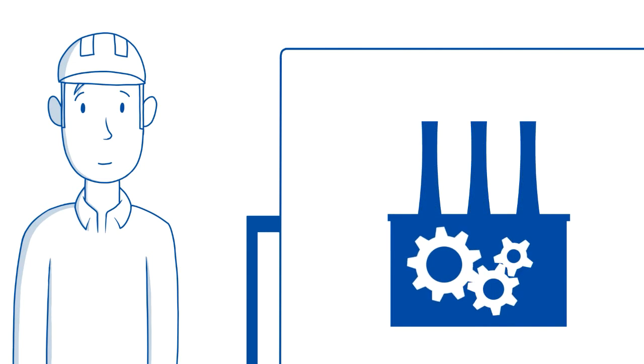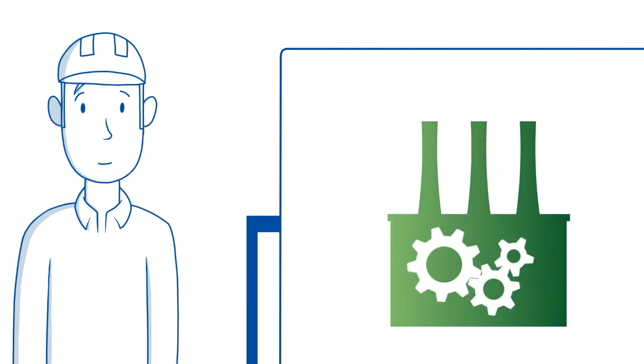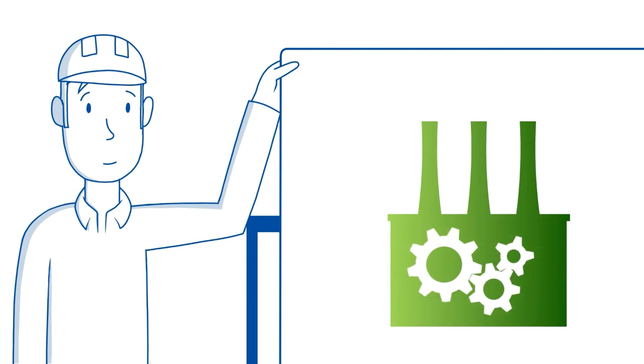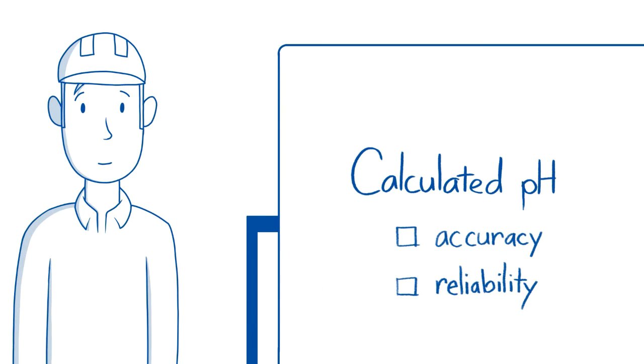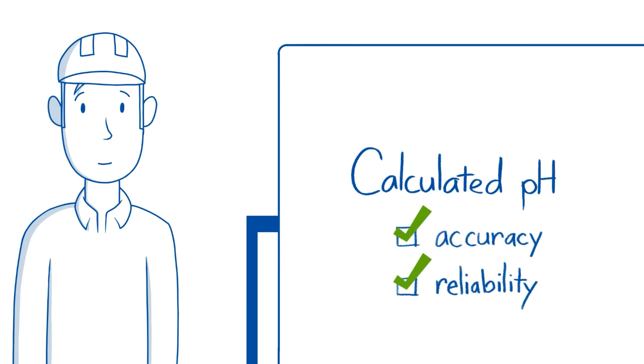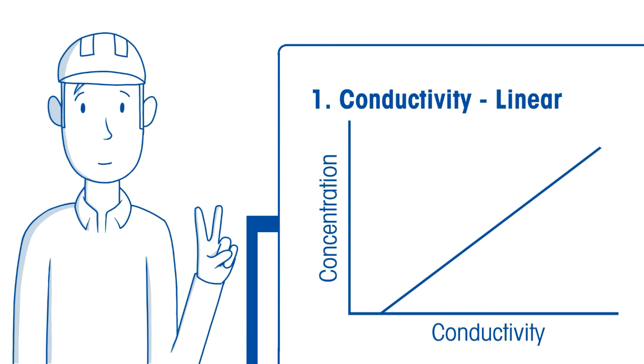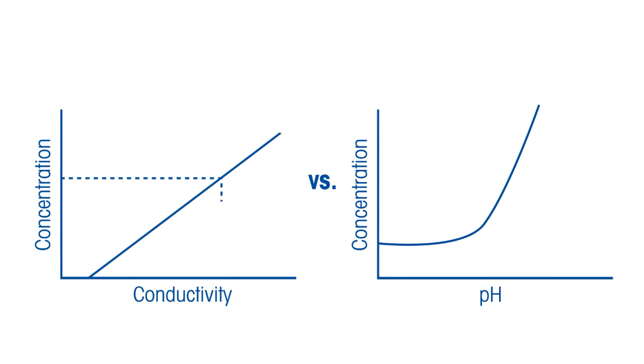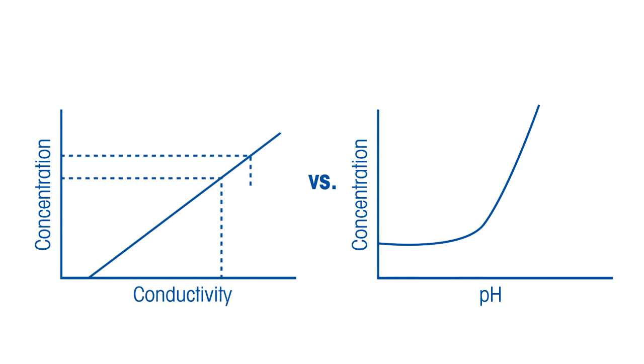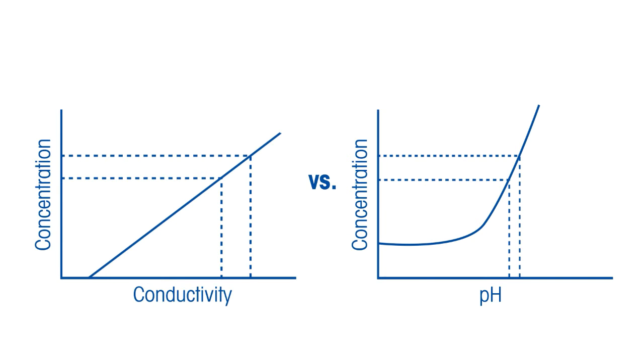Under normal operating conditions, this calculation provides more accurate and reliable results than pH electrodes can provide for two reasons. First, conductivity is linear with concentration, which provides much higher resolution than pH sensors, all of which give non-linear response to concentration.